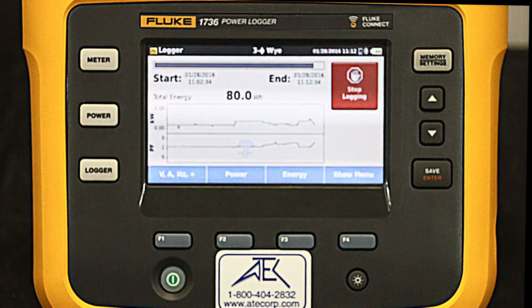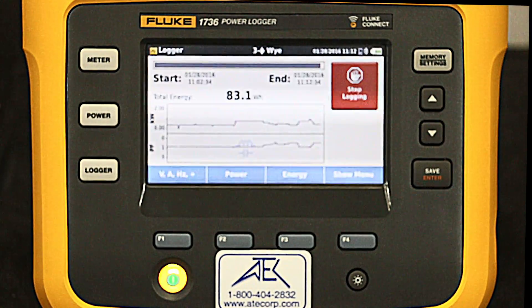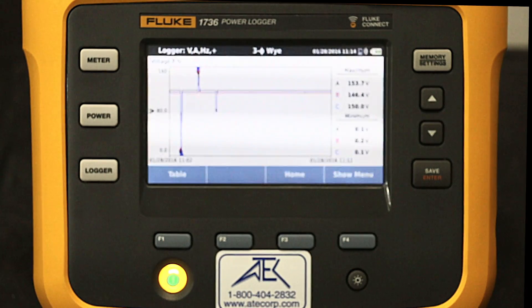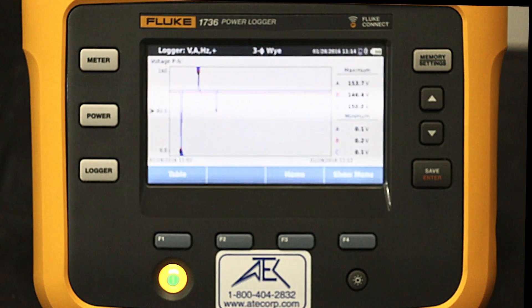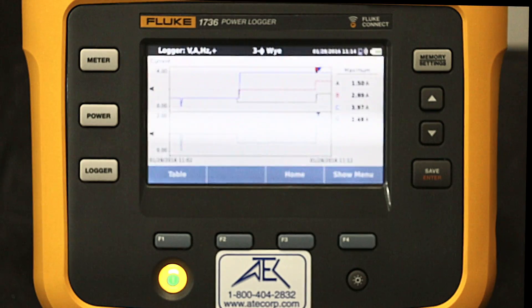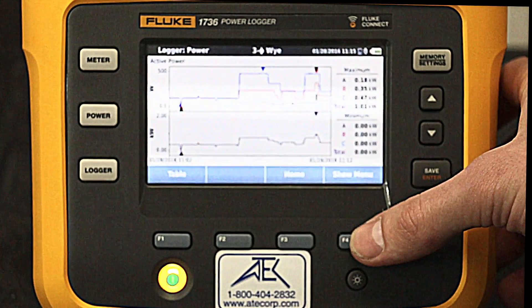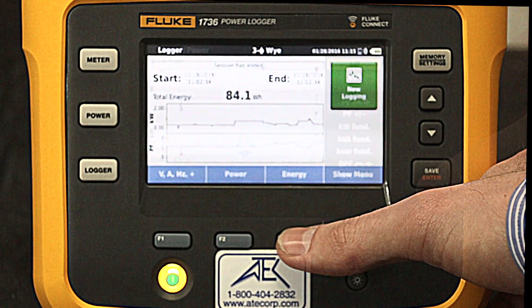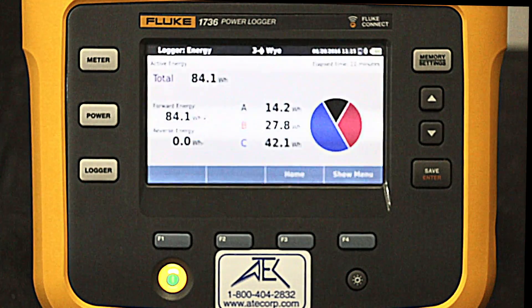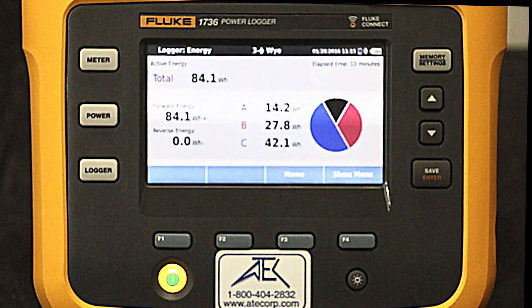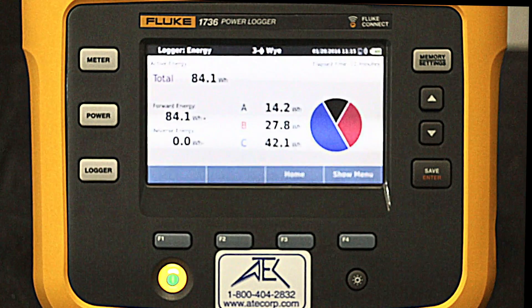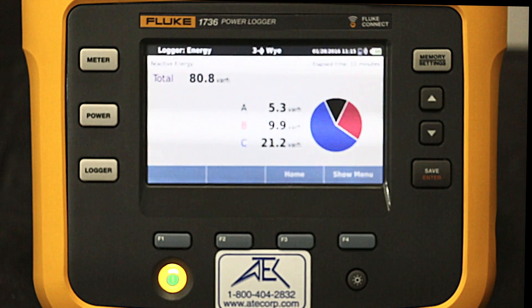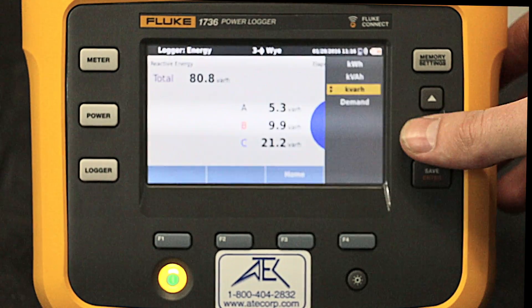Let's fast forward to the recording session and look at the captured data. Here we can see the interrupt, swell, and dip that occurred, as well as what happened to our current and power. Looking at the graphical view, we can see that Phase C drew the most current. We can also look at Volt-Amperes, Reactive, and Demand.